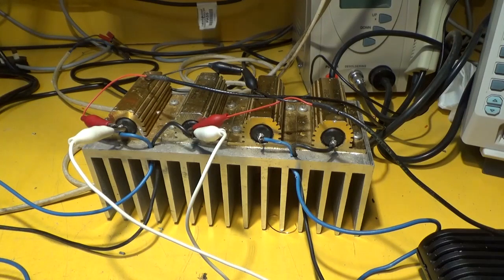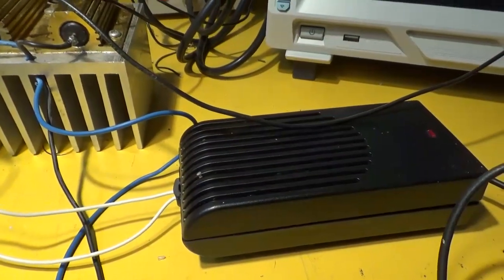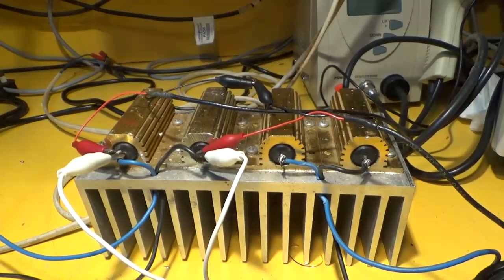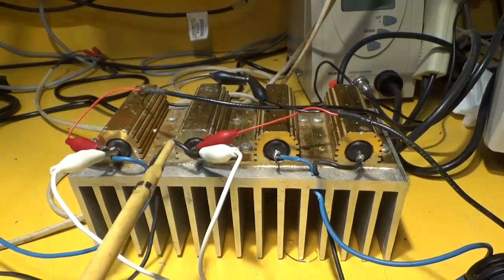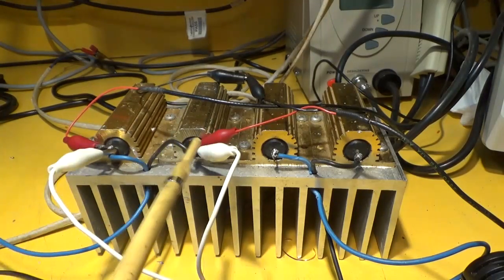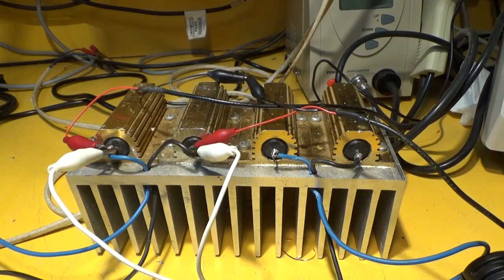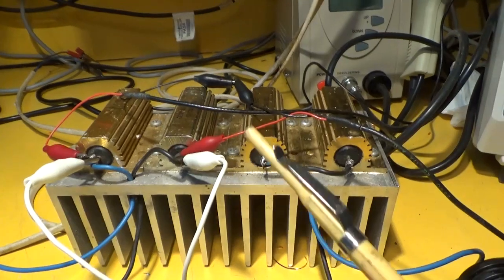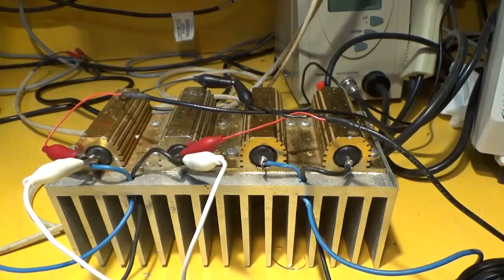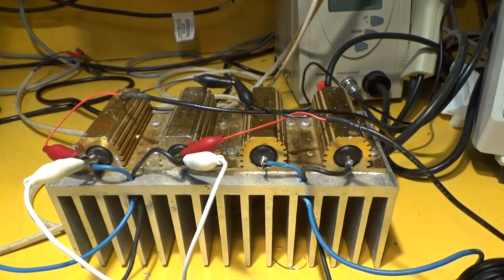So the way around that one is you have a differential probe, which is this little black box I built a few years ago. Now that's measuring on the white cables, and it's a differential probe. It's measuring the difference between those 2 connections, obviously, and then converting it to a single-ended output reference to Earth, which I can now look at on the scope. And also, you see the red clips, they're connected to my HP audio analyzer, which has an option to have a single-ended input or a differential input. So I've got that set to a differential input. In other words, it's measuring the signal across those red cables and not down to Earth. So that explains the test setup.